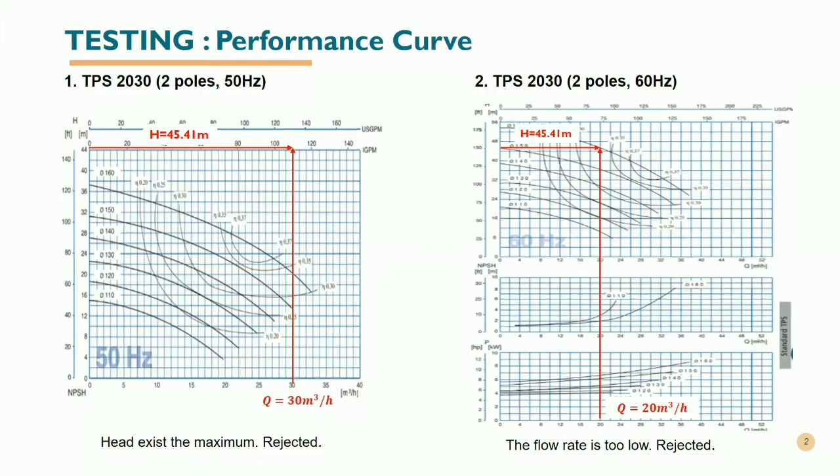We need to test specific pumps by using their performance curves. The first pump we tested is the TPS 2030 with two poles and 50 hertz. From the graph, when the head is 45.41 meters and the flow rate is 30 meter cubed per hour, the head actually exceeds the maximum head of this pump, so this pump is rejected.